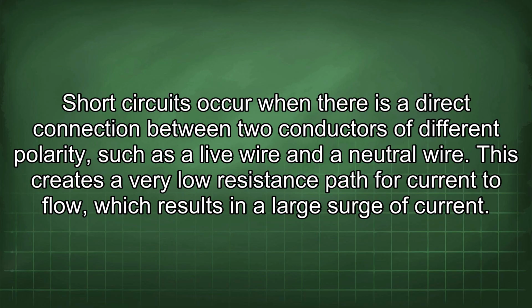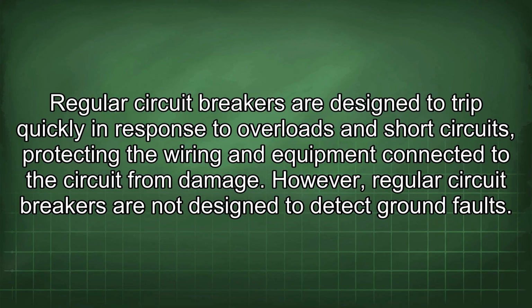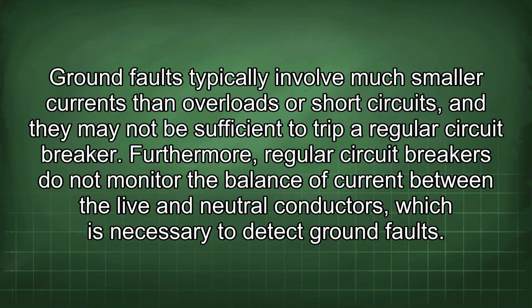Short circuits occur when there is a direct connection between two conductors of different polarity, such as a live wire and a neutral wire. This creates a very low resistance path for current to flow, which results in a large surge of current. Regular circuit breakers are designed to trip quickly in response to overloads and short circuits, protecting the wiring and equipment connected to the circuit from damage. However, regular circuit breakers are not designed to detect ground faults. Ground faults typically involve much smaller currents than overloads or short circuits, and they may not be sufficient to trip a regular circuit breaker. Furthermore, regular circuit breakers do not monitor the balance of current between the live and neutral conductors, which is necessary to detect ground faults.